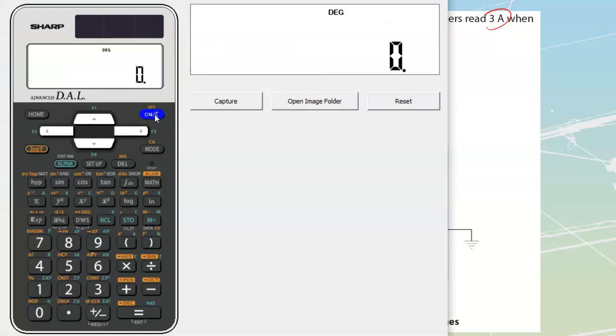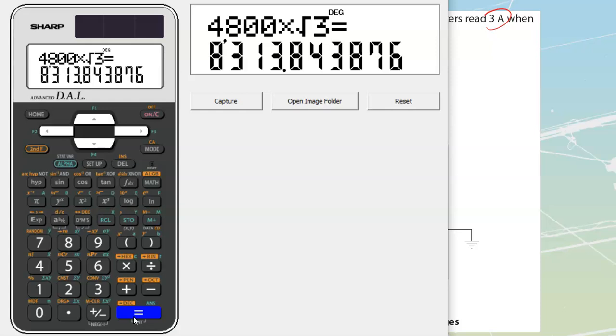We know that our current was given in the question as being 4,800 times root 3, which gets me out to a value of 8,313 amps. It's a little bit higher than what is shown inside of your book over here. Inside of your book, it's showing 4,800 over 5 over 3, etc. Off of these ones here, and the current ratios, etc. The primary line current that they're showing you over here, they just do this thing backwards.